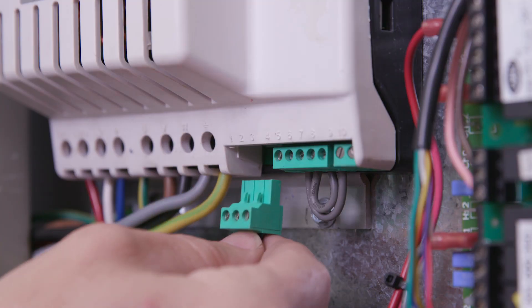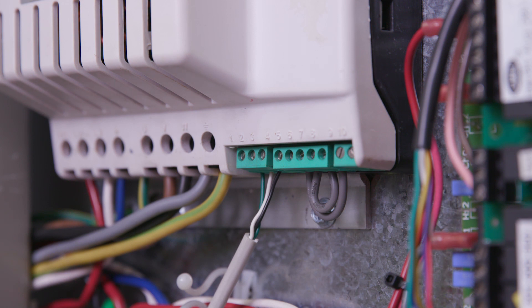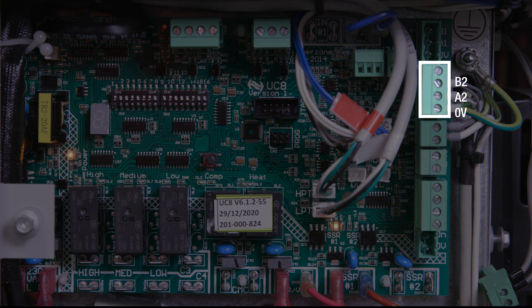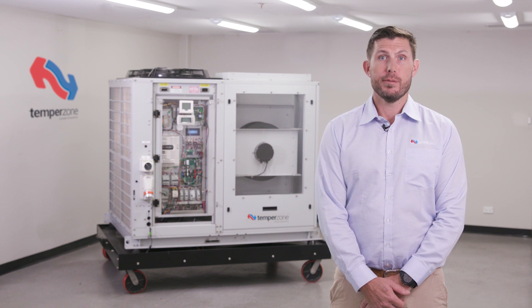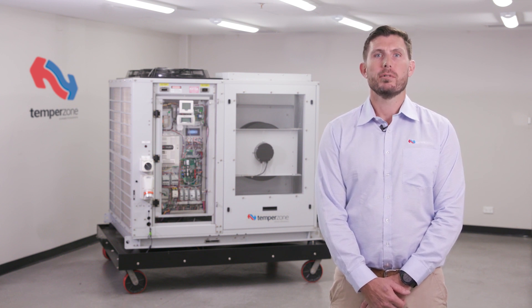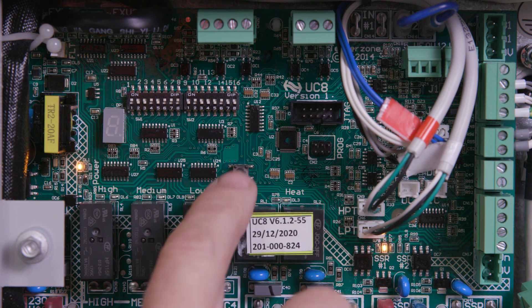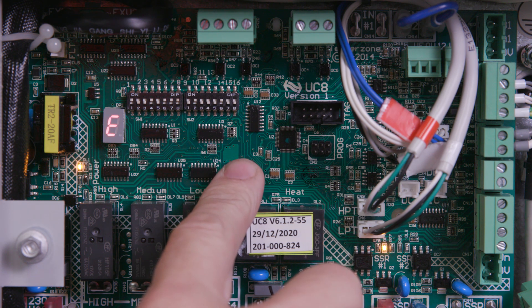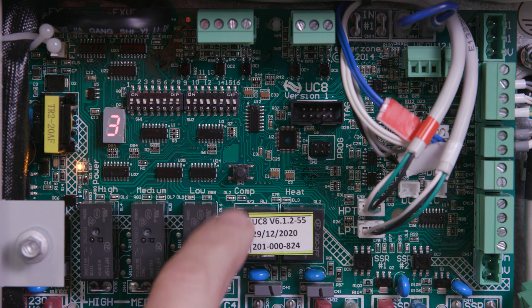temperzone uses high-level Modbus communication to send and receive commands via RS485 cable connected from the A2, B2, 0V terminals on the UC8 board. One advantage of using Modbus communication is the ability for the UC8 to program a unique set of operational parameters for specific compressor models through the compressor selection function within special mode E of the UC8. Modbus communication also allows for high-level fault information to be sent to the UC8 display.